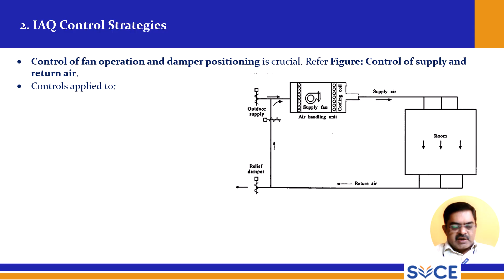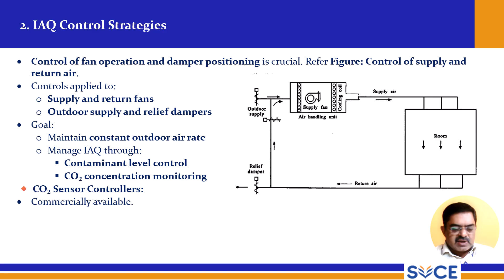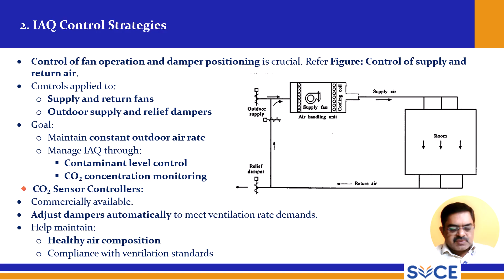Controls are applied to supply and return fans, outdoor supply and relief dampers. The goal here: maintain constant outdoor air rate, manage IAQ through contaminant level control, and CO2 concentration monitoring. CO2 sensor controllers are commercially available, adjust dampers automatically to meet ventilation rate demands, help maintain healthy air composition, and ensure compliance with the ventilation standards.